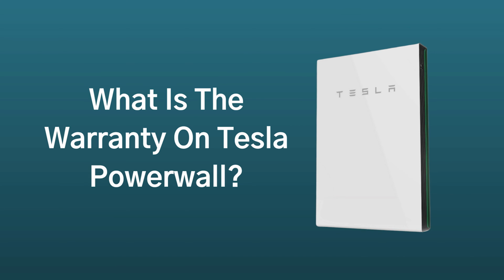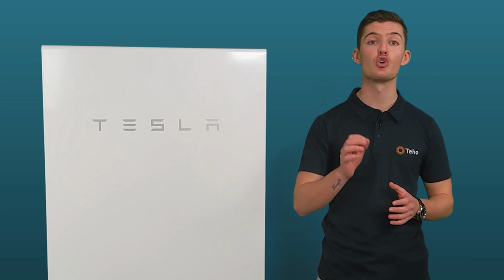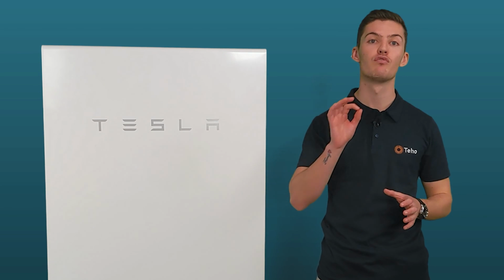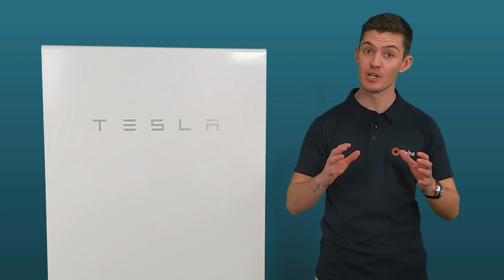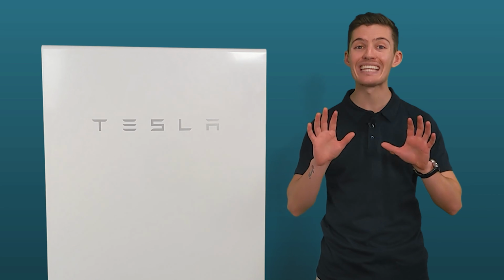What is the warranty on Tesla Powerwall? There are a few layers to the warranty of Powerwall. The breakdown of the warranty is in a table on the warranty document. The first part of the warranty states that if you're using Powerwall for solar self-consumption, time-based control, and backup, the battery will maintain 70% of its capacity following the initial installation date for unlimited cycles across a 10-year period. Basically, if you're using your Tesla Powerwall in a pretty standard setting, then the warranty will cover you for 10 years and guarantee 70% usable capacity relative to the 13.5 kilowatt hour output from day one for unlimited cycles.